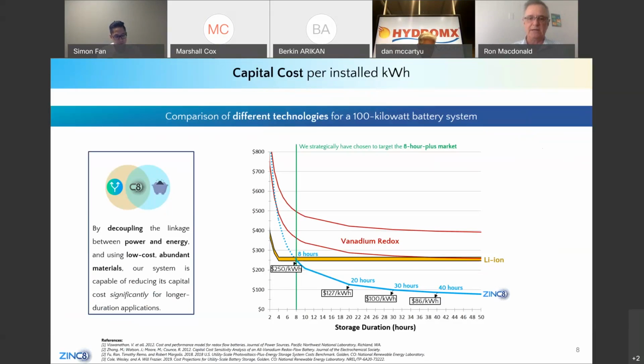I want to talk about this briefly, as it's the reason we're getting a lot of attention. This shows a comparison of different technologies for a 100 kilowatt battery system and cost per kilowatt hour stored. Lithium-ion owns the space under 4 hours and can perform well economically up to about 6 hours. Then their economics flatten, for the reason Simon mentioned, because power and energy are tied in a 1-to-1 ratio. Vanadium redox batteries are a great technology, I've been involved with it for a long time.